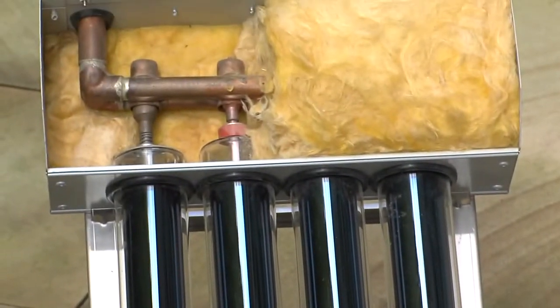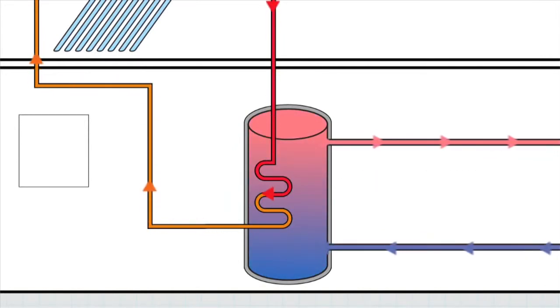In places with minor frosts, evacuated tubes may offer enough inbuilt protection. In climates with regular frosts, indirect or closed loop systems are the most popular and reliable form of frost protection. Instead of water, an antifreeze fluid is heated in the collectors. The antifreeze passes heat onto the water via a heat exchanger. The antifreeze does not come into contact with the household water supply.